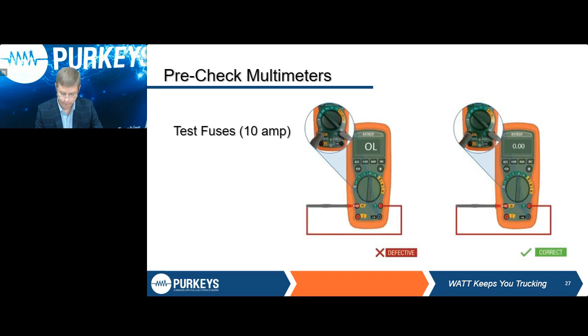Before you use that meter, you can check that internal fuse without opening up the meter. Again, put your meter on ohms, take your red lead and put it up in the port where your 10 amp lead should go. That allows you to check the resistance of that fuse inside and tell you if it's good or bad. Again, on most meters, if it's good, it's going to give you a very low or a 0 ohm resistance reading. If it's blown, it's going to give you an OL. Now, there are always some exceptions. Someone's going to have some weird meter I'm not familiar with, but that's a pretty good standard rule of thumb to check that fuse.